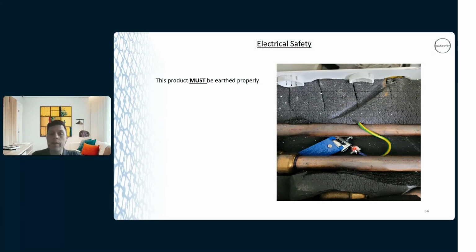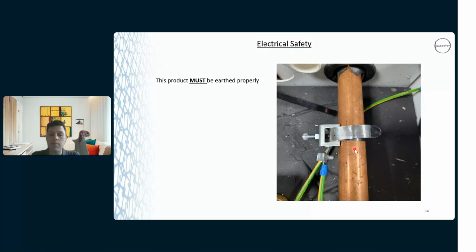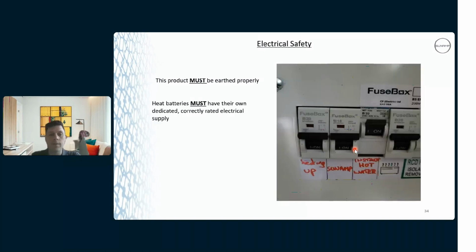What the earth clamp is doing is completing the earth circuit of the heat battery, so it has to be fitted. And it's just a regular earth clamp, 10 mil squared. It must also have its own dedicated electrical supply.